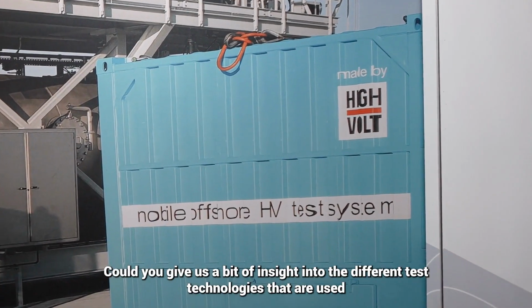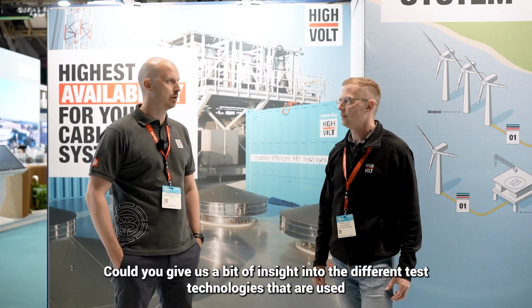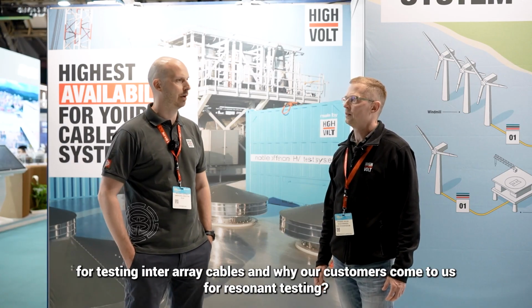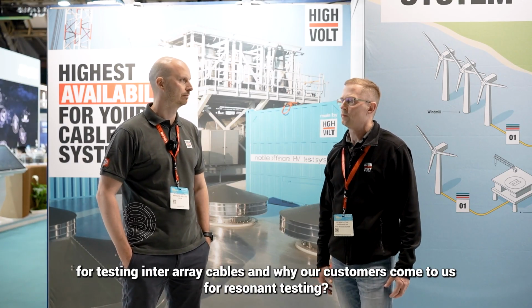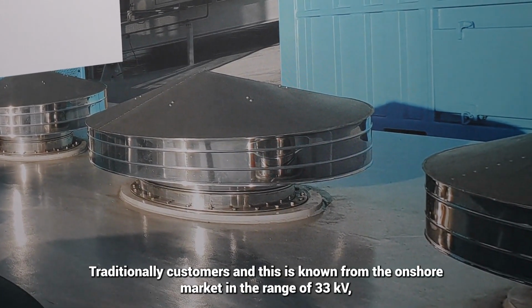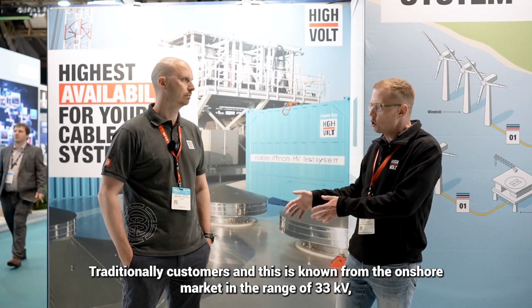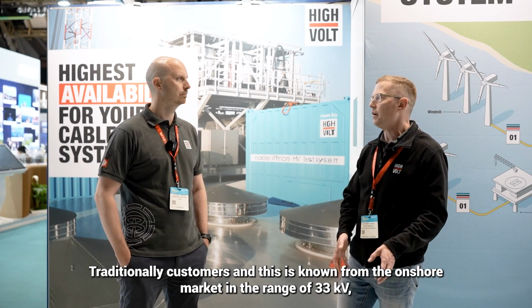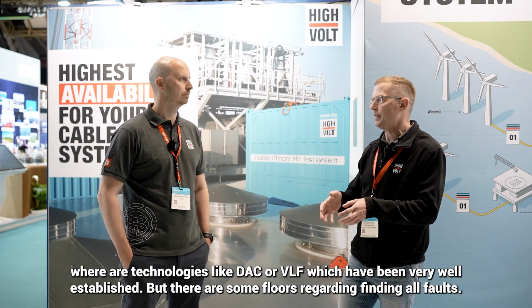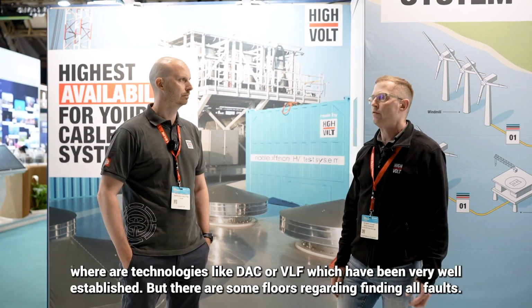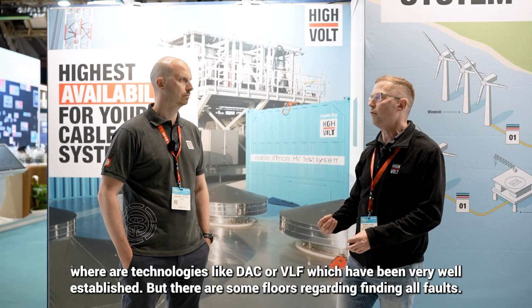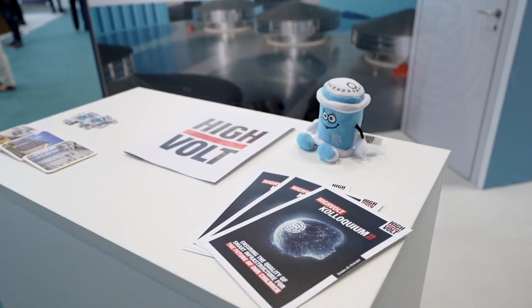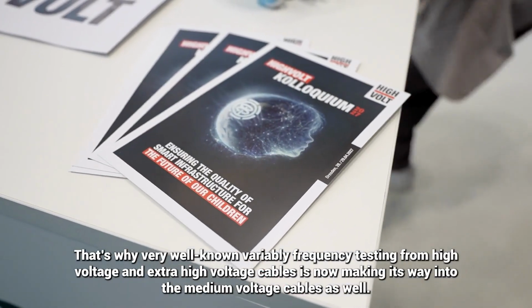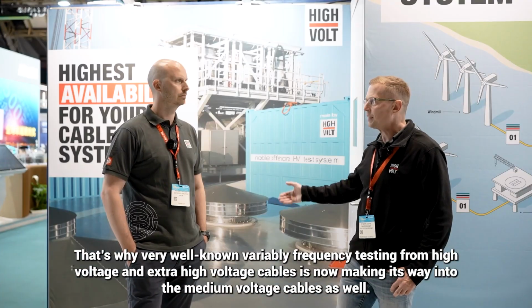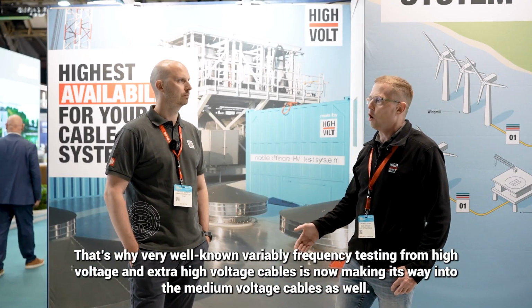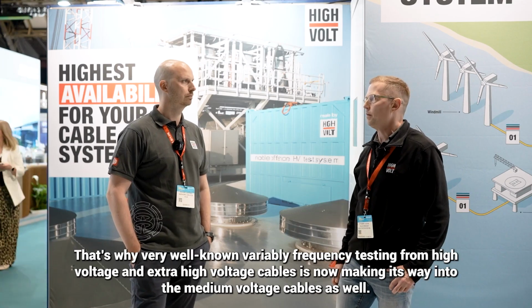Could you give us a bit of insight into the different test technologies that are used for testing inter-array cables and why our customers come to us for resonant testing? Traditionally, customers, and this is known from the onshore market in the range 33 kV, use technologies like DAC or VLF, which have been very well established, but there are some flaws regarding finding all the faults. That's why very well known variable frequency testing from the high voltage and extra high voltage cables is now making its way into the medium voltage cables as well.